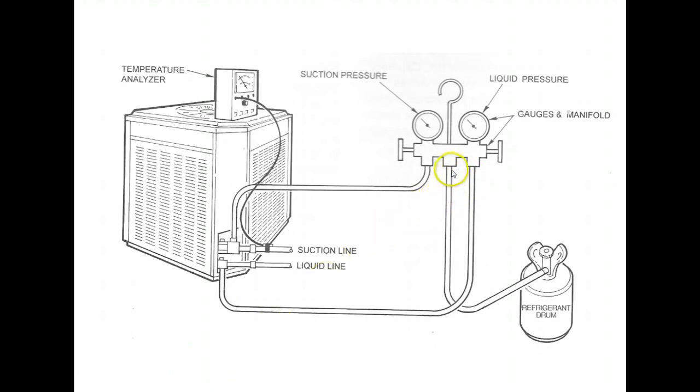And then you'll do that for the third time over here on the yellow hose once you have your refrigerant drum hooked up and your valve on the drum open so that you have some refrigerant pressure here. Loosen up your hose and allow some refrigerant to purge out and tighten it up. And now you've purged the air out of all three of your refrigeration lines.